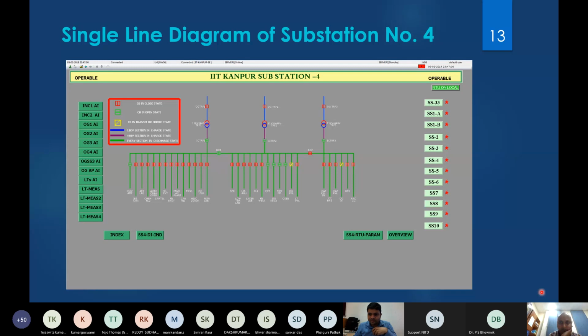At substations, whenever you have an RTU, it measures both instantaneous power and cumulative energy. All this information comes from the RTU to the control center. Not just energy, but frequency and power quality parameters, power factor, everything is available at the control center for all substations. SCADA gives you individual power flows in the lines, voltage, current, power factor, up to 415 volt outgoing lines in the 11 kV substations. That kind of information is available at the control center.